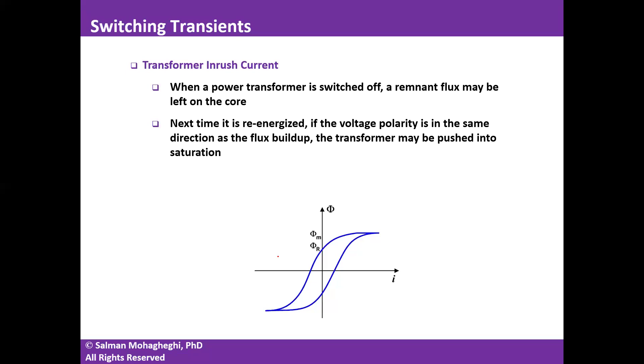The last event we'll discuss is transformer inrush, which we have seen before in the context of harmonics. When you switch on a transformer, you might have a wide variety of harmonics. The reason is that when you switch it off, some remnant residual flux may remain in its core. Next time you energize it, depending on the polarity of voltage, flux may build up on top of that residual flux — pushing very deep into saturation and causing very high currents heavily polluted with harmonics.